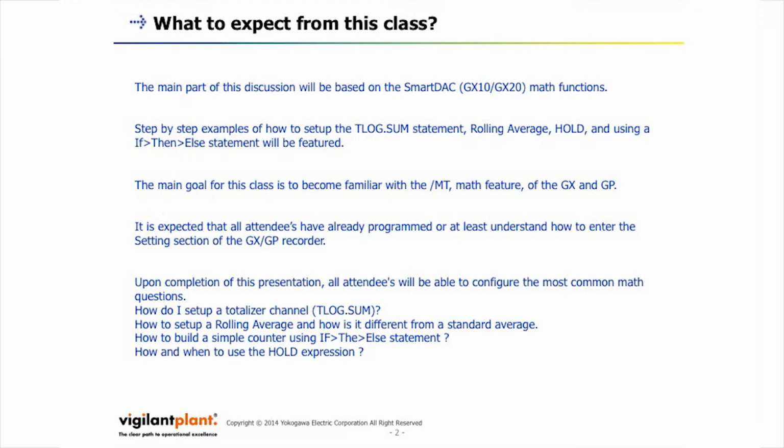Upon completion of this presentation, all attendees should be able to configure the most common math questions that arise. How do I set up a totalizer using a tlog.sum? You'll see that in an example. How to set up a rolling average and how it is different from a standard T-log average. How to build a simple counter using an if-then-else statement, and how and when to use the hold expression.